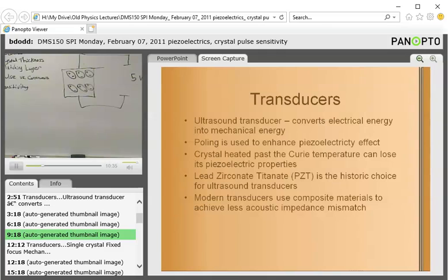The other thing that happens is all the epoxy that holds them together falls off, and then you've just got a bunch of wires sticking out of your end of a, and it's really not nice. Yeah, that's exactly what I was going to say. Wires sticking out of the end of a wire. But it all falls apart. It's held together with epoxy. Epoxy will break down at about 150 degrees Celsius. The Curie temperature is maybe about 400 to 500, so it really isn't the Curie temperature we're hitting in the autoclaves, but you don't want to heat these things up is the point. They will lose their piezoelectric properties.